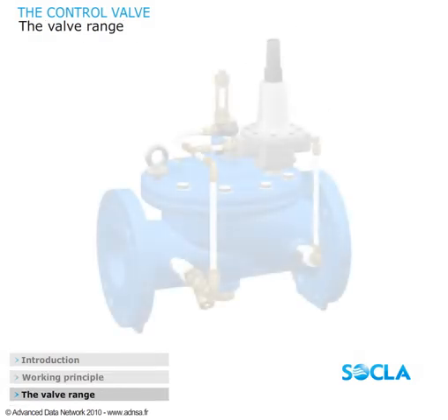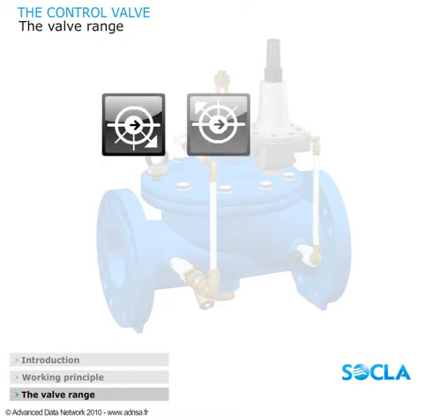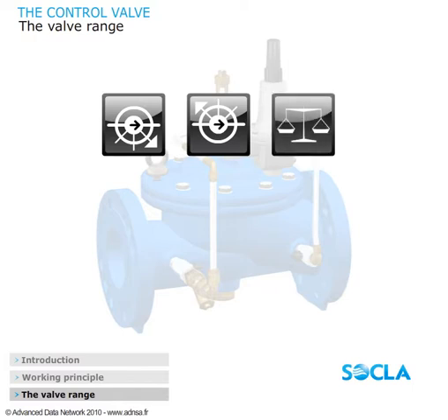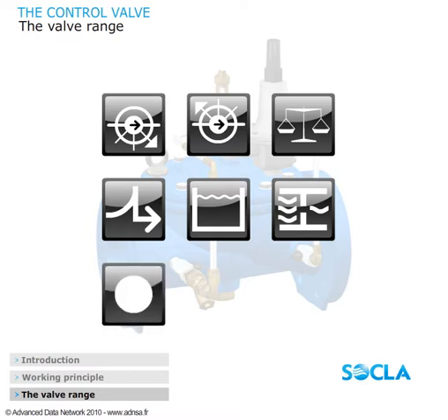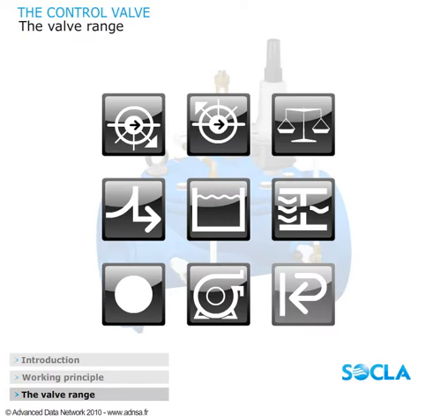Thanks to a combination of different pilot valves, the control valve can control downstream or upstream pressure, maintain a differential pressure, evacuate overpressures, control a level, control flow, obtain total opening of the valve, protect a pump, and act as a check valve.